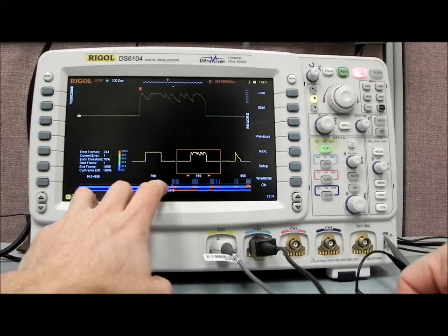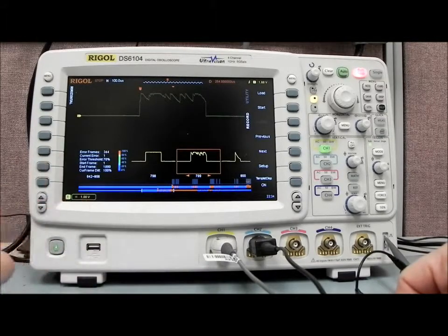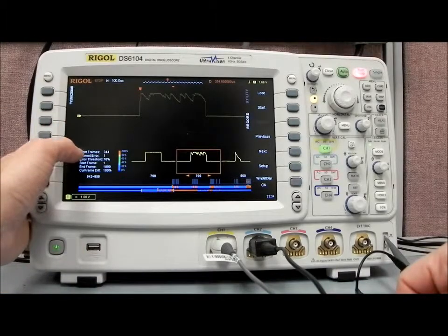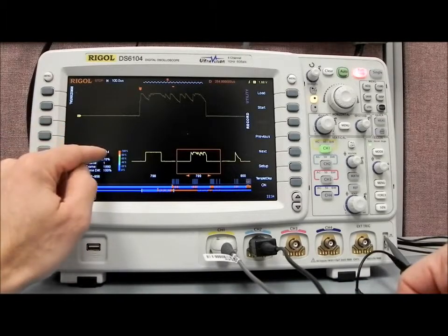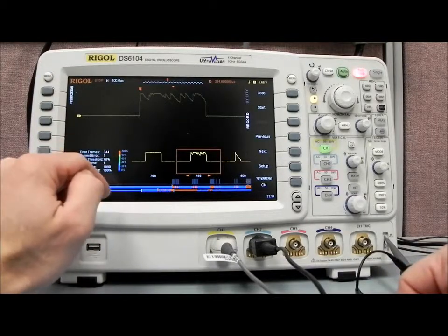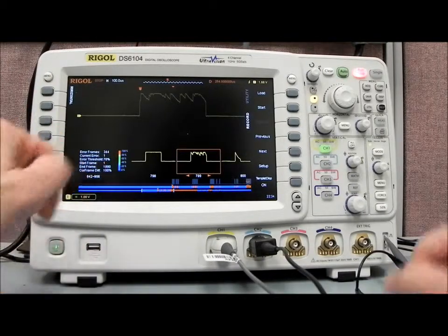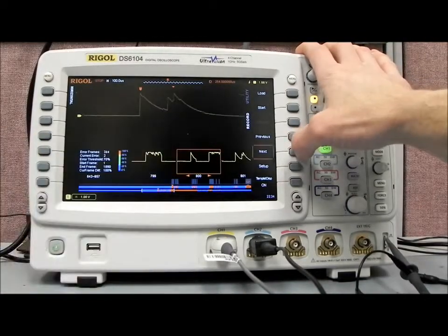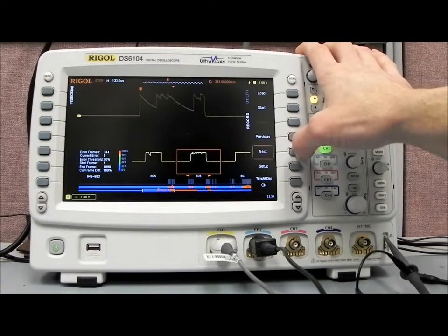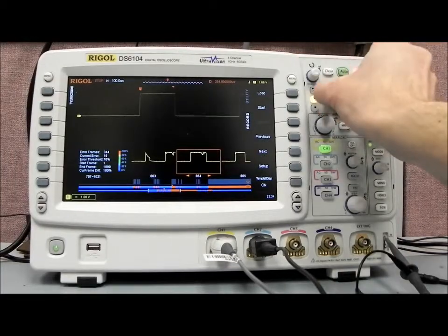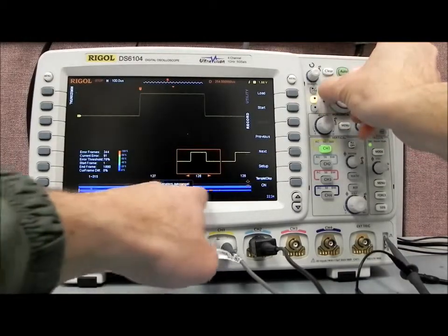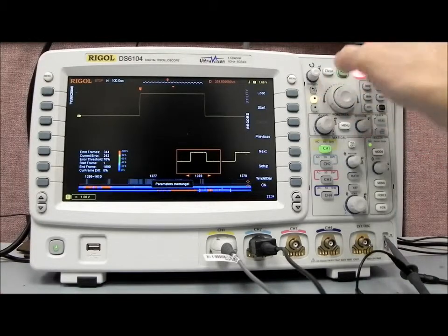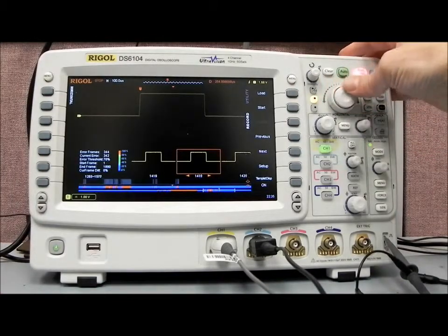The center area is a zoom into the different frames that we have failed, and on the left-hand side it tells us how many error frames we have. So this is 344 out of the total, which was 1,890. You can very easily go using previous or next to each of the failed waveforms. You can cycle through each and every failed waveform, or you can use the fast forward key and slide along very quickly through that entire waveform, or you can go one frame at a time by using the inner knob like that.